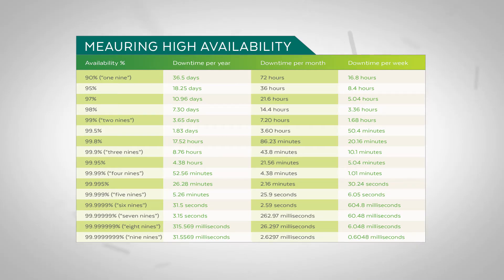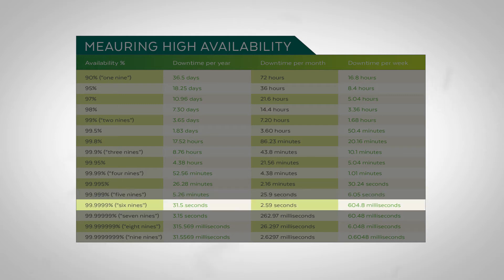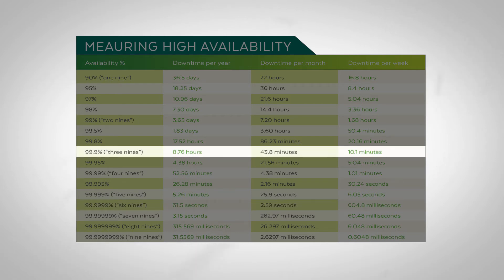This is critical, as technology teams can often get lost in the technology, so it's important that the remedy is not worse than the affliction. The question of how much availability do I need is kind of like asking how long a piece of string is — it completely depends on the impact the outage would have on your company. Now let's talk about how availability is measured. This table shows a widely accepted methodology for measuring downtime. Most have probably heard of the 5-nines as a standard for measuring availability. In order to claim 5-nines, all of the outages for a system added up can total no more than 5.26 minutes in a year, assuming a 24 by 7 operation. Most companies would be thrilled just to achieve 3-nines, or a total downtime of 8.76 hours for the system annually.